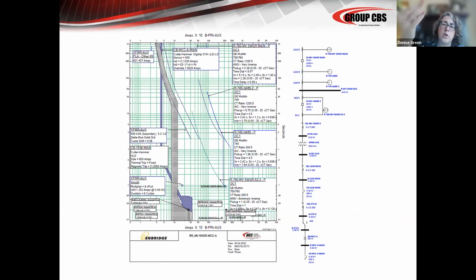And so I like to include this so you can see that the selection of time bands is not random in your coordination study. It directly relates to all of the components in your system, and that's how the settings are generated: by what substructure, what fuses, what equipment is there, and the availability of changing settings, so that if there is a fault, items open in the proper order. You don't want a whole single-ended substation going offline because a little motor on the roof locked up and your breaker that was supposed to shut that off didn't trip. So that's just the whole coordination study view.